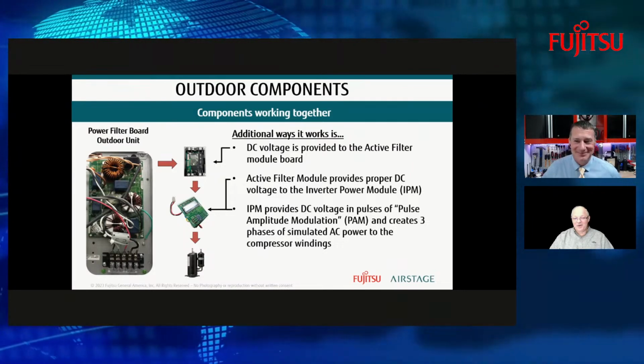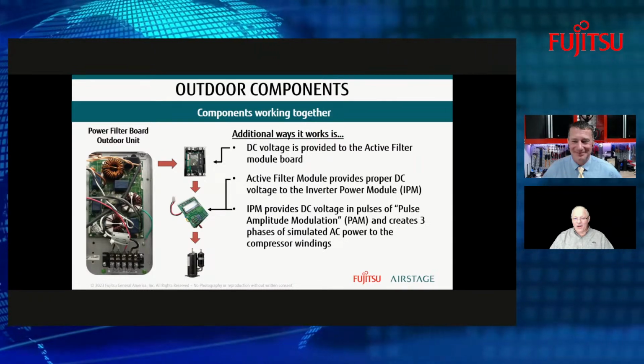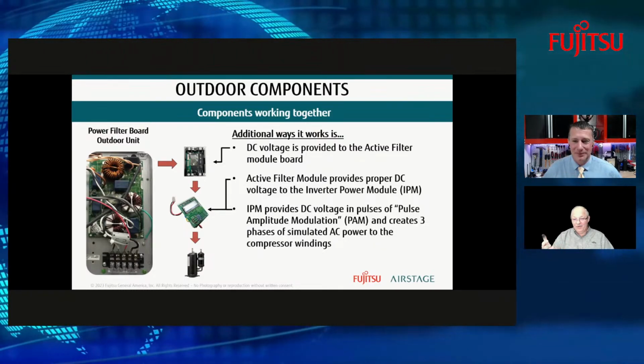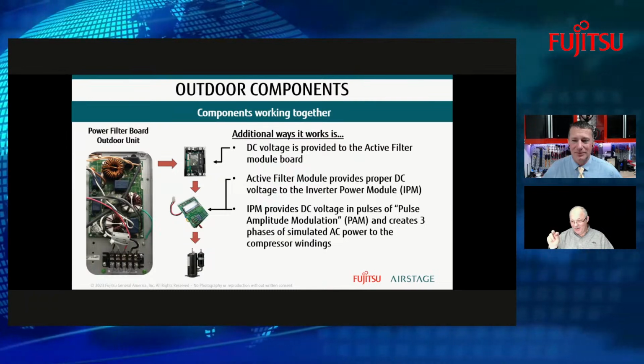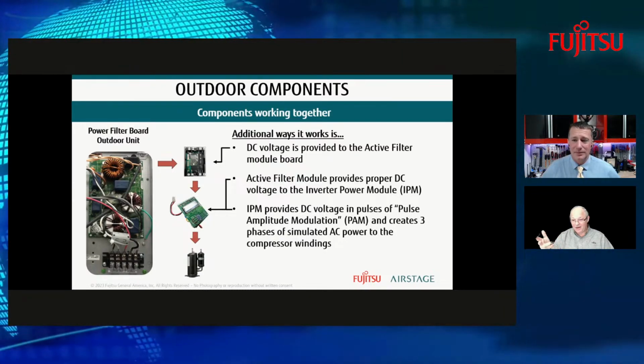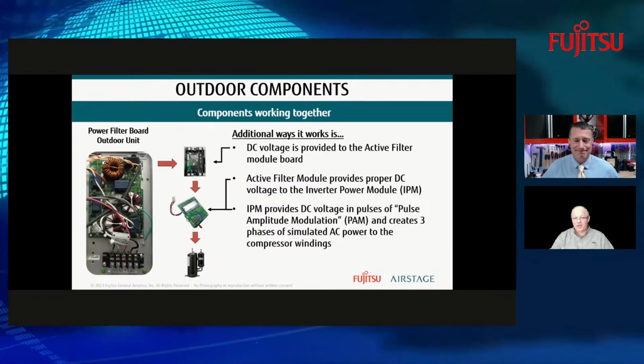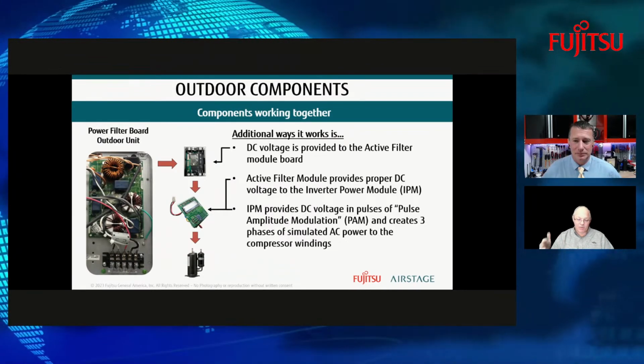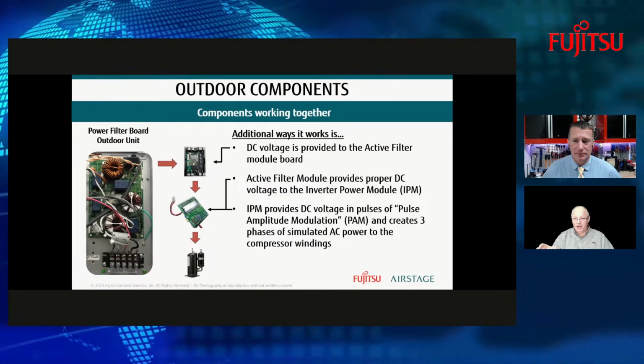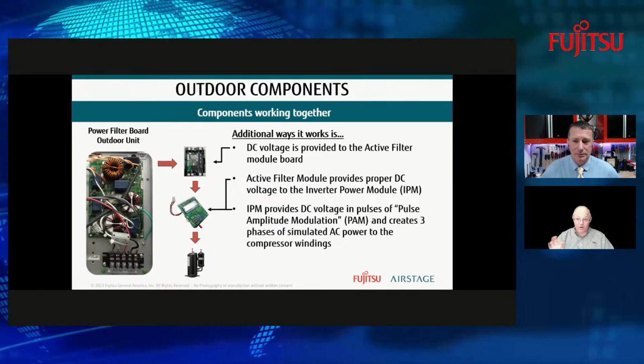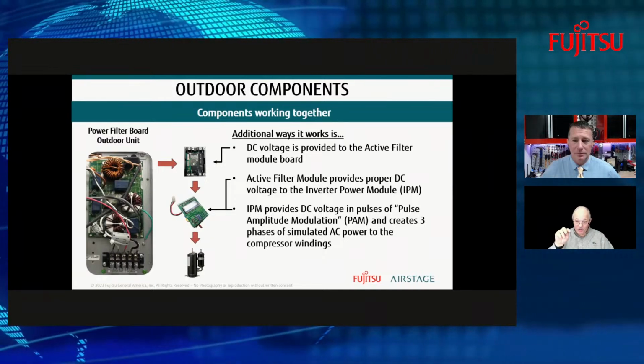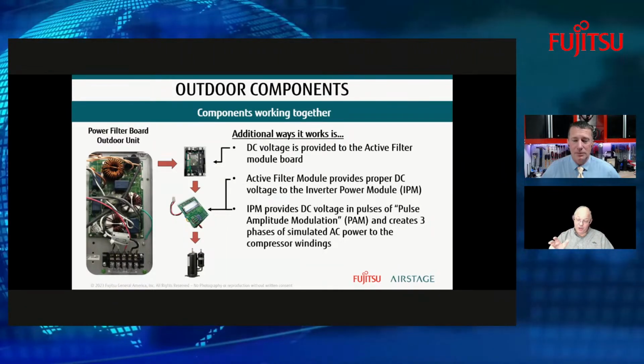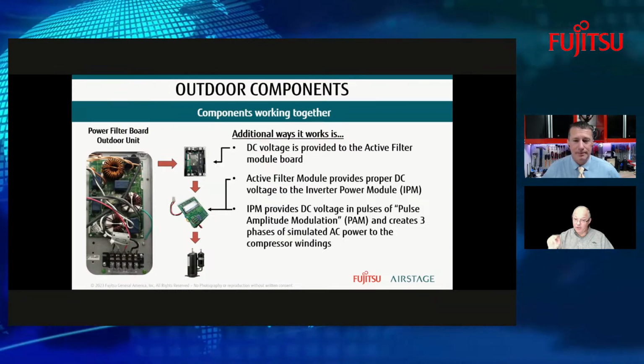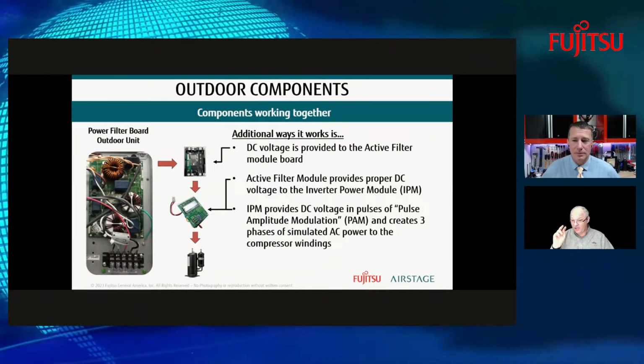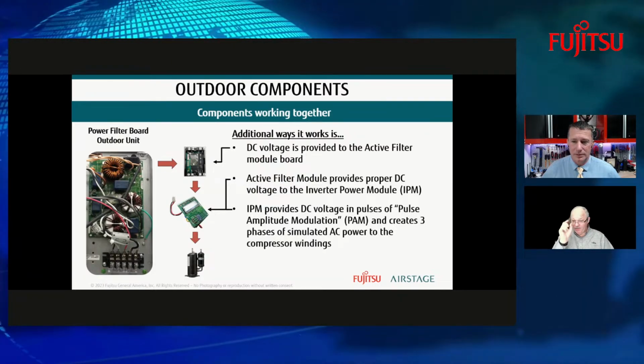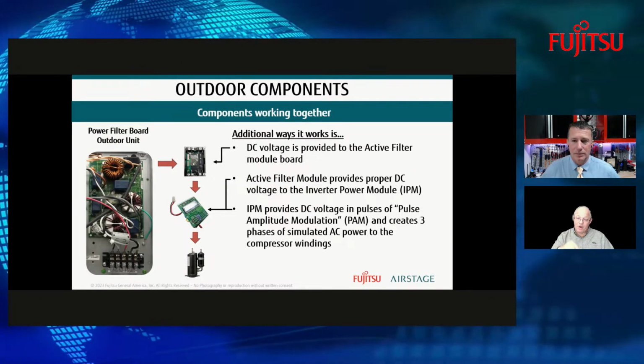Yeah. So whenever you take a reading and you go into actual literature, if it tells you to check from here to here, it'll tell you what that voltage is going to look like. That's right. So the manuals that you get, whether it be a service manual or service instructions, regardless of the inverter that's out there, they'll actually tell you what your voltage reading should be, and you should see it fluctuate. Okay. If you just get a number that doesn't fluctuate, if it's just one number and it won't move, then you've got a problem with the board.